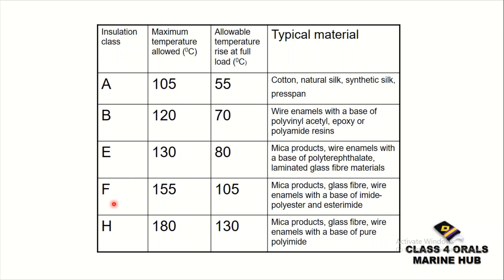Next is Class F insulation. The maximum allowed temperature is now increased to 155 degrees centigrade, and the allowable temperature rise at full load is 105 degrees. The typical materials include mica products, glass fiber, and wire enamel with a base of imide-polyester and esterimide.